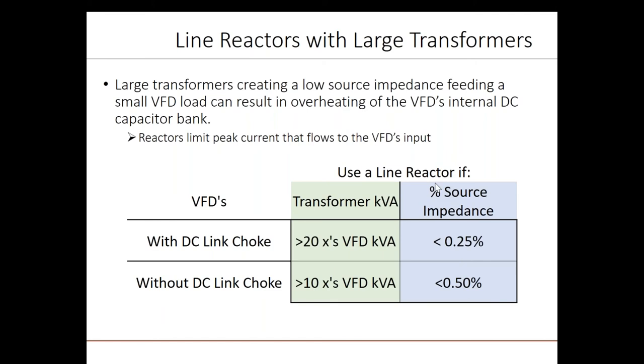It's common that a VFD may be powered by a transformer that is significantly higher in power rating. A large transformer appears as a low impedance source to the VFD, which can cause overheating of the internal DC capacitor bank. The larger the transformer, the lower the impedance will be relative to the size of the VFD. As a rule of thumb, use a line reactor if the drive does not have a DC-link choke and the transformer supplying the drive is larger than 10 times the VFD's equivalent KVA rating. If the VFD does have a DC-link choke, consider adding a line reactor if the transformer's KVA is greater than 20 times the VFD's equivalent KVA rating.